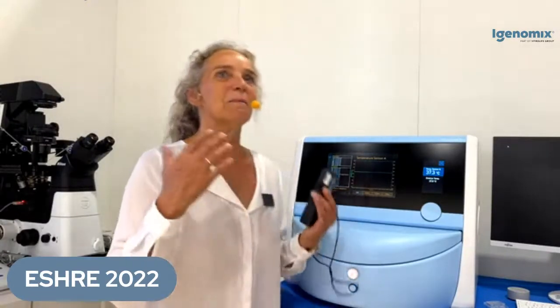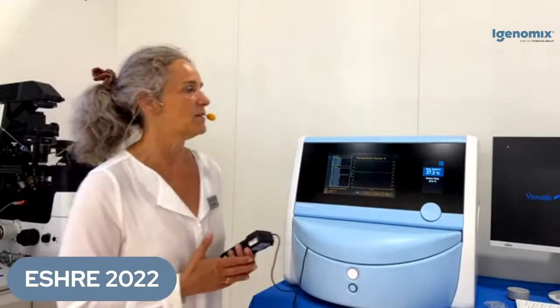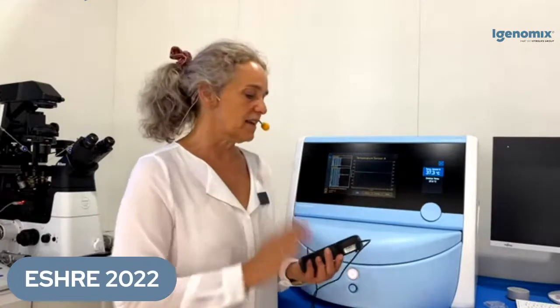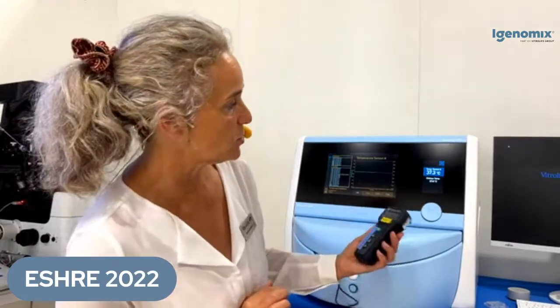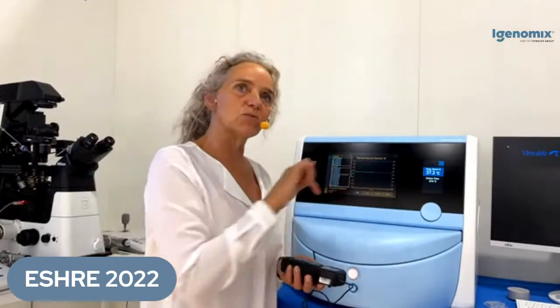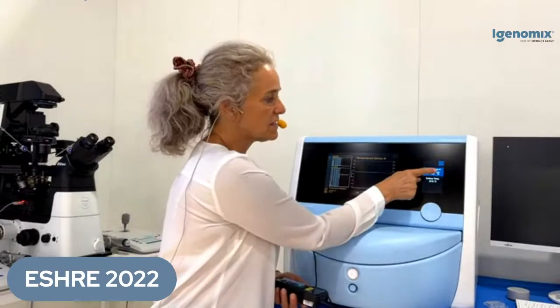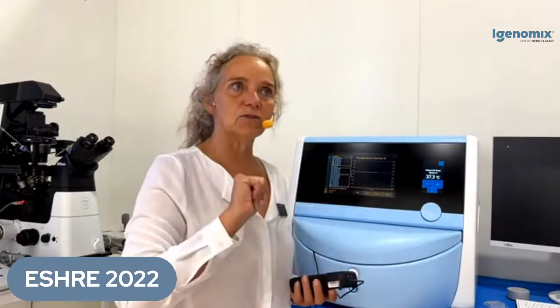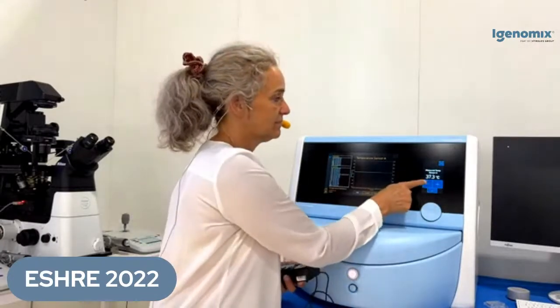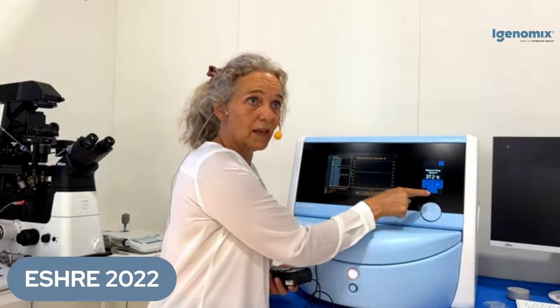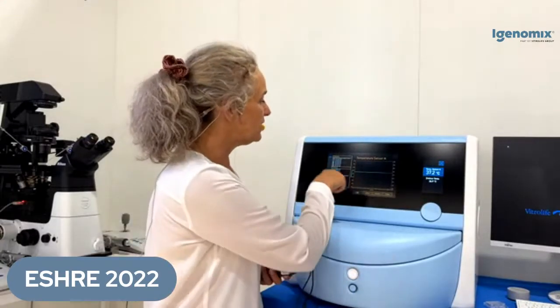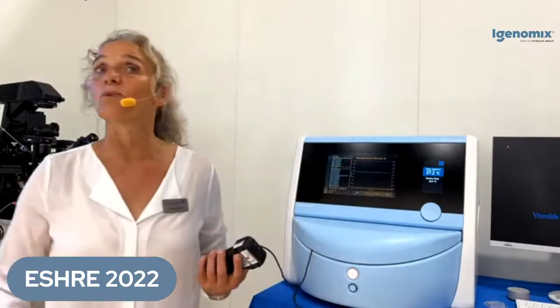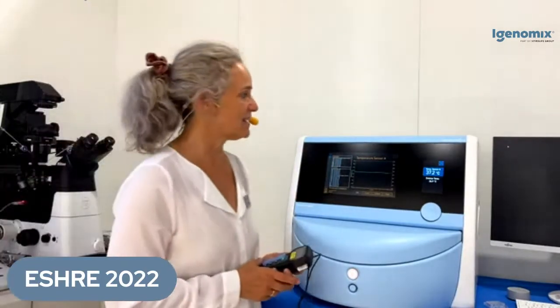We don't have time for that now, but I'll just show you how you calibrate them if you have to calibrate. So let's pretend, now it's actually showing 37.2. What I would do is match what is on my analyzer. So here I press on the sensor A, and then I will calibrate minus 0.1. And then I press on confirm. I press here, and then you start calibrating. Again, you will see here on the screen that everything I have done is documented. Okay, so that's clear.